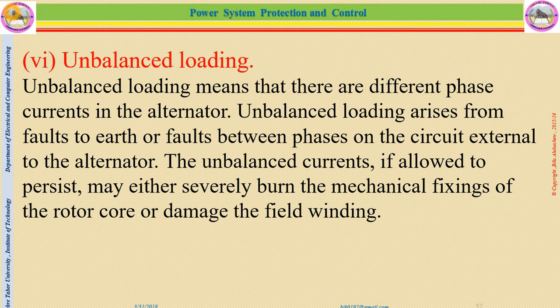The sixth fault of the generator is unbalanced loading. Unbalanced loading means that there are different phase currents in the alternator. Unbalanced loading arises from faults to earth or faults between phases on the circuit external to the alternator. The unbalanced currents, if allowed to persist, may either severely burn the mechanical fixing of the rotor core, or damage the field winding. So this unbalanced load is of several types of faults, and we must give automatic protection for unbalanced loading.